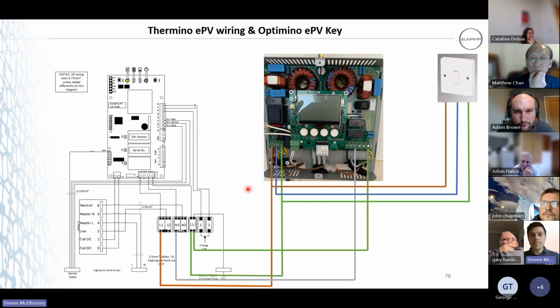So ePV. Yeah, we do have a 4-core. Don't be fooled by this at the moment. We've got a permanent live coming in, powering the PCB essentially. All right, so in this scenario, what will happen is we don't have any PV being generated. If you look there, we've removed link 1 between L1 and L2.